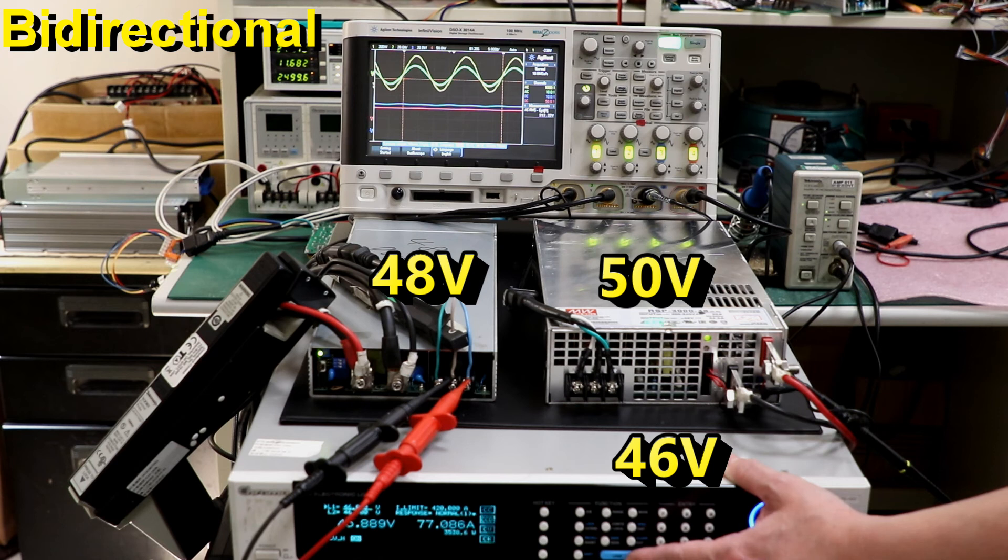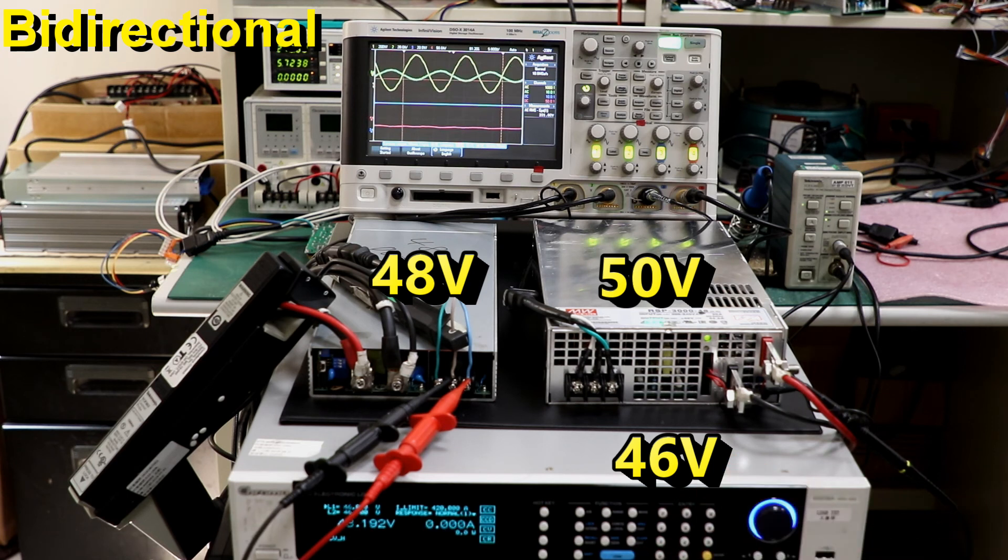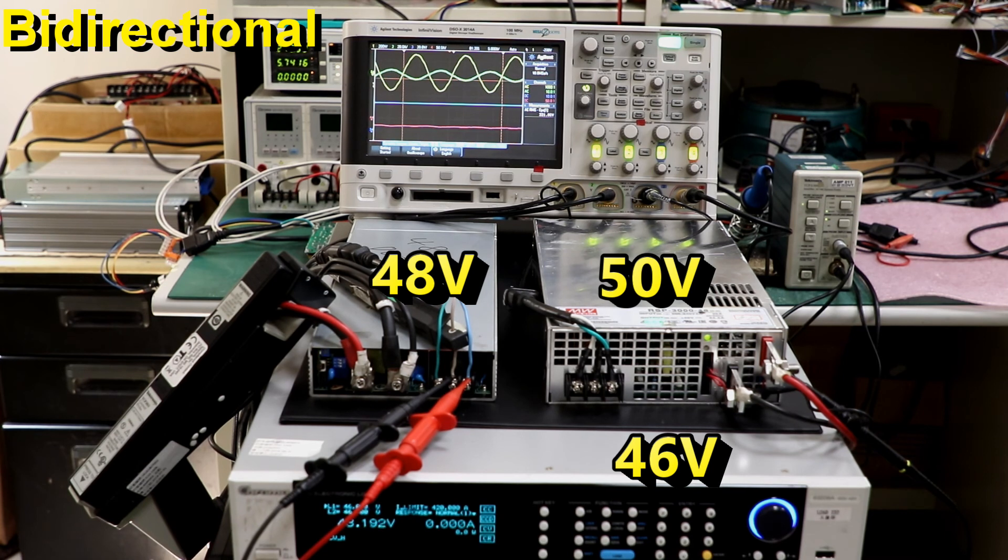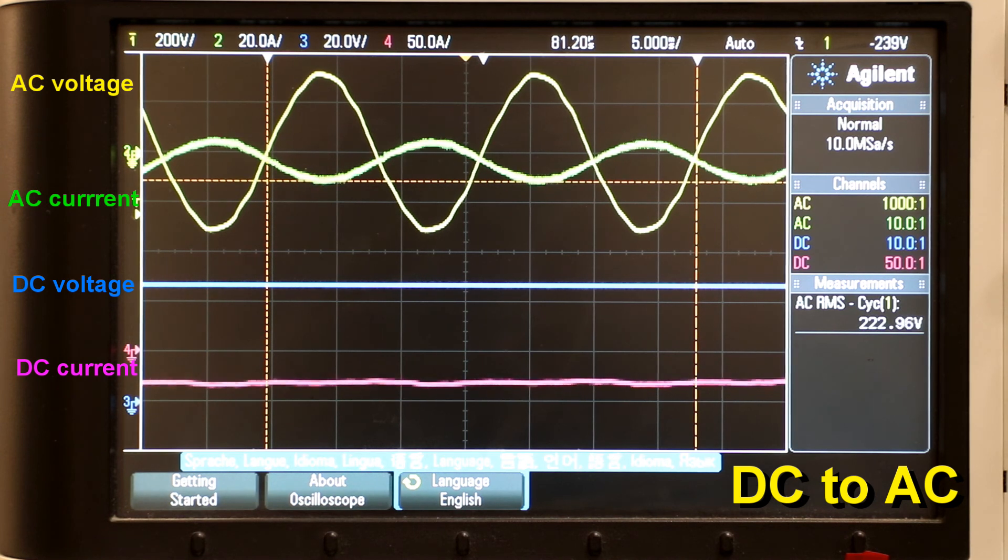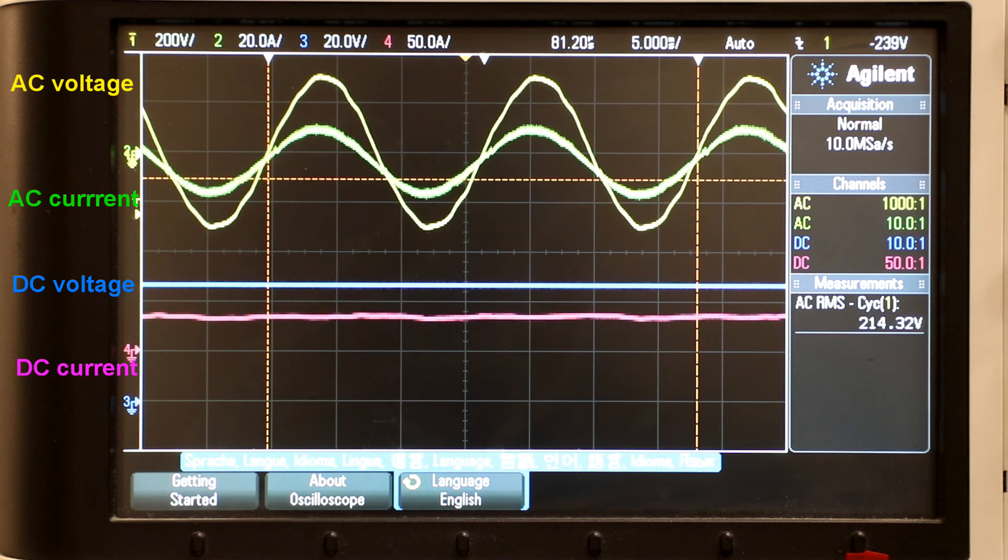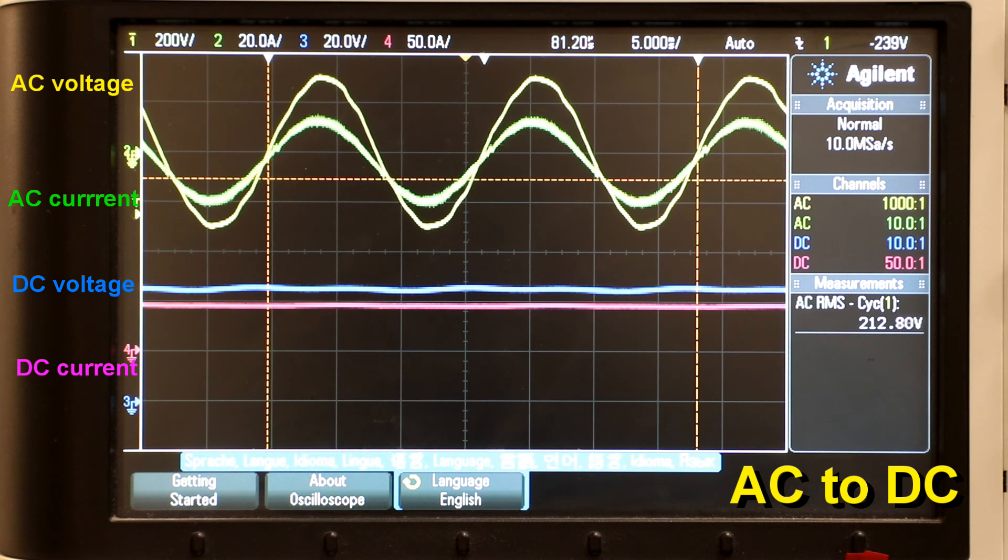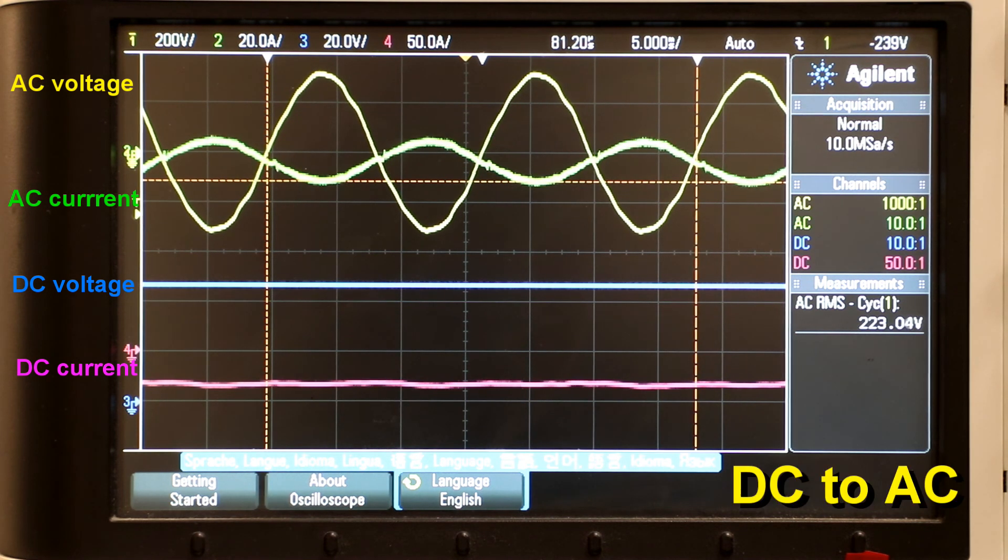Turn the electronic load on then off to let the DC end voltage of the BIC fluctuate between 46 volts and 50 volts to test its bi-direction auto-detect function. From the waveform of the oscilloscope, we can observe that the BIC switches between AC to DC and DC to AC conversion automatically according to different voltage at the DC end.